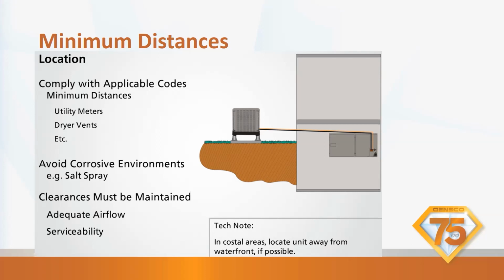Maintain your clearances, adequate airflow, make sure you have serviceability. I know that the book says 24 inches, but what about electrical code? Electrical code's 36 inches. So we need to remember that although we only need 24 inches for the mechanical code, the electrical code says 36. So you need to be careful how you install that equipment.